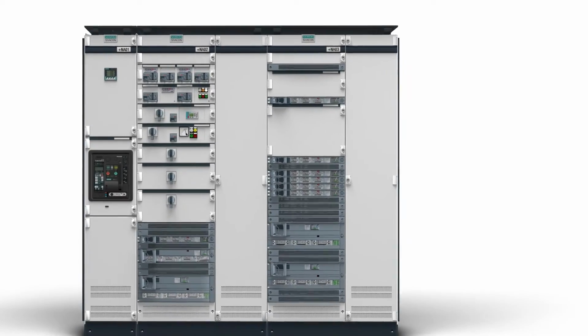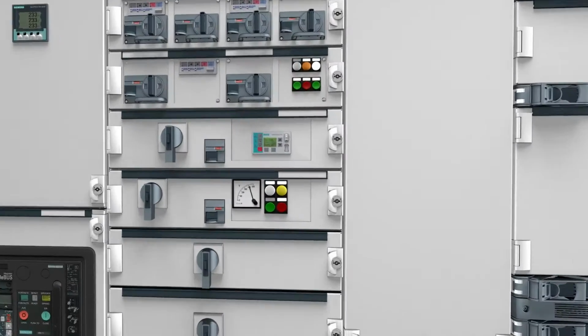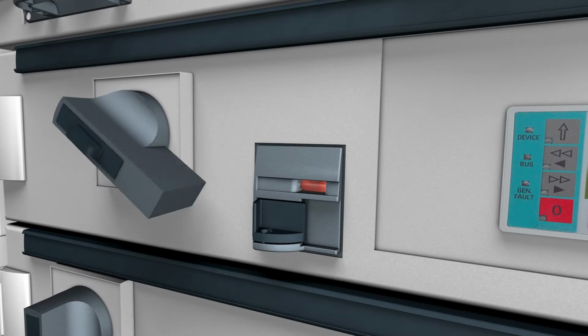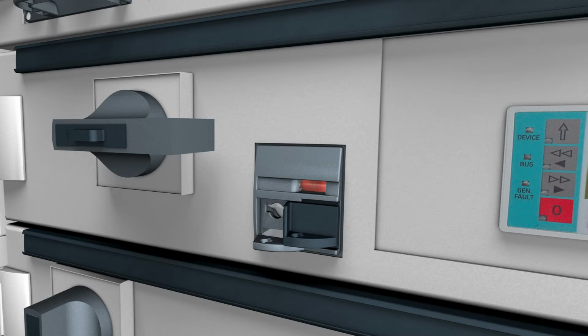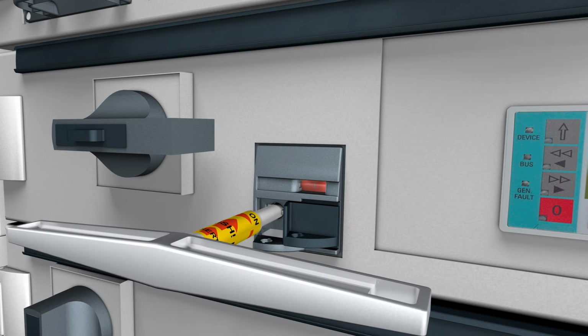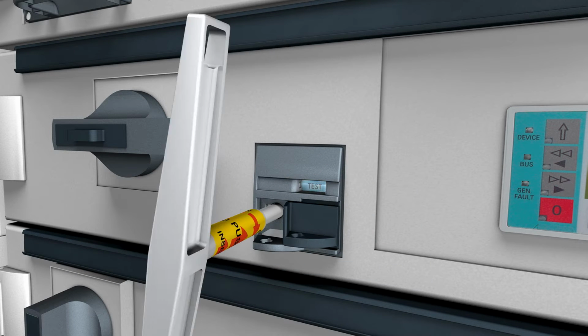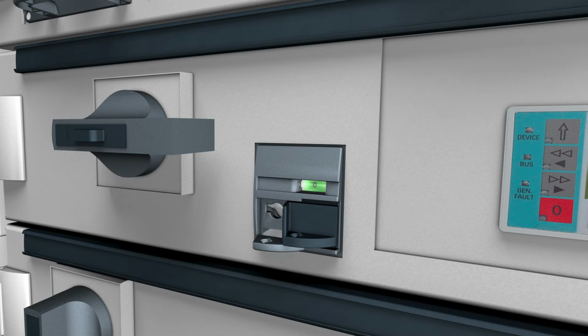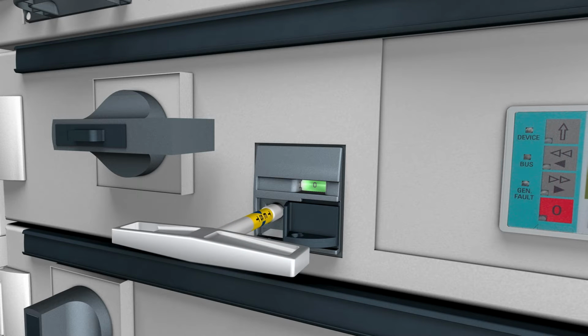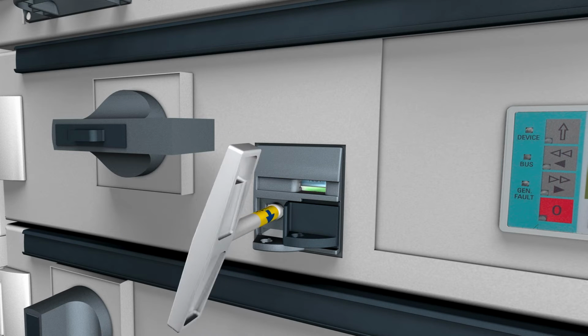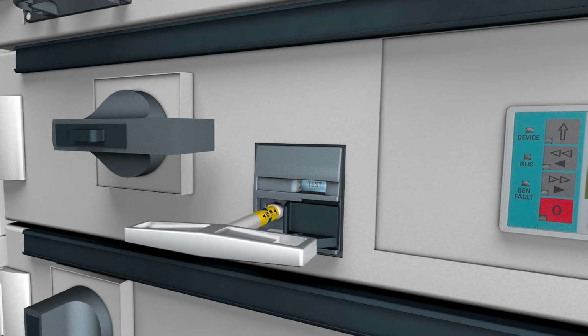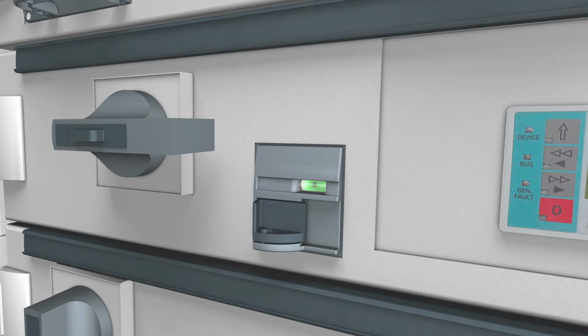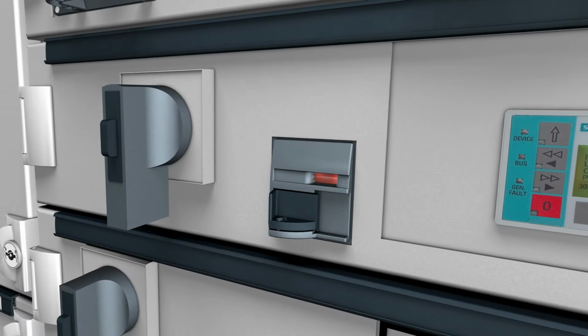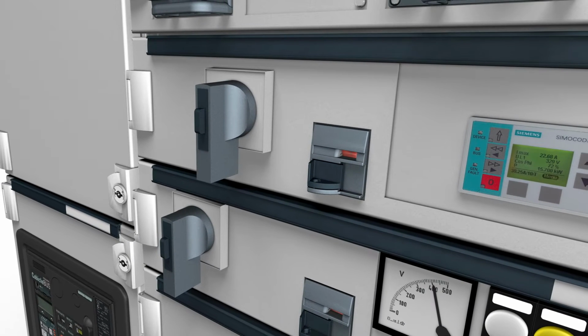The operating patterns are uniform for all withdrawable unit sizes. The withdrawable unit's connected, test, and isolated positions can be set with the door closed. This ensures high operator protection at all times. The degree of protection and the arc resistance are maintained. The integrated operation fault protection supports easy and safe handling.